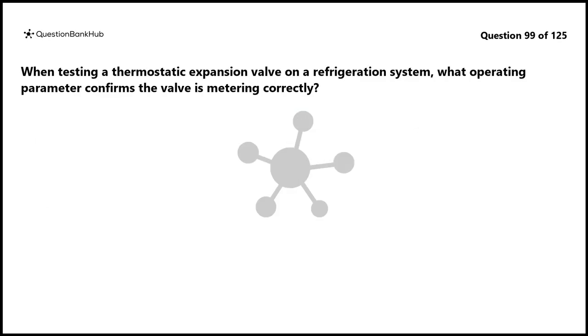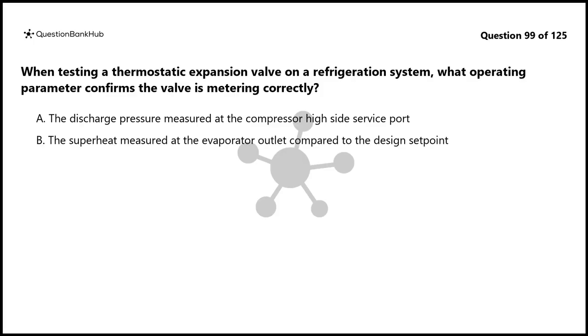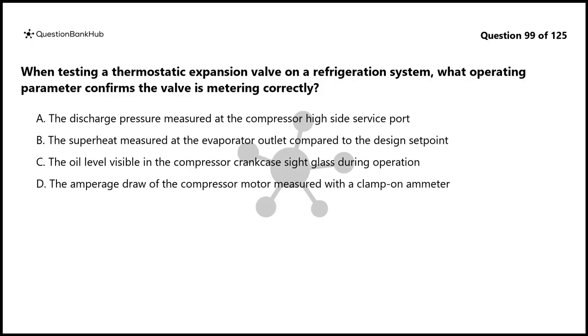Question 99. When testing a thermostatic expansion valve on a refrigeration system, what operating parameter confirms the valve is metering correctly? A. The discharge pressure measured at the compressor high side service port. B. The superheat measured at the evaporator outlet compared to the design setpoint. C. The oil level visible in the compressor crankcase sight glass during operation. D. The amperage draw of the compressor motor measured with a clamp-on ammeter.